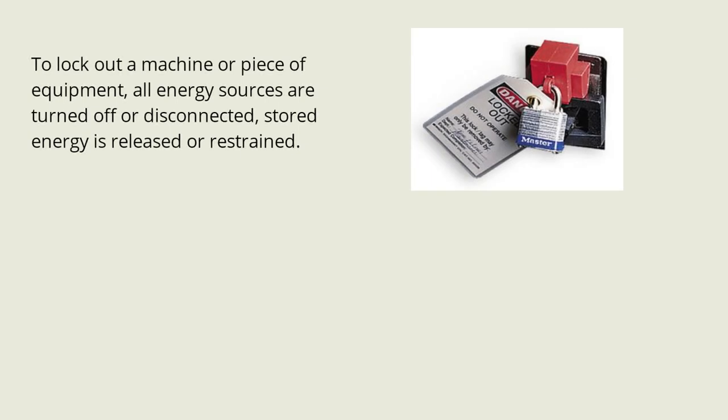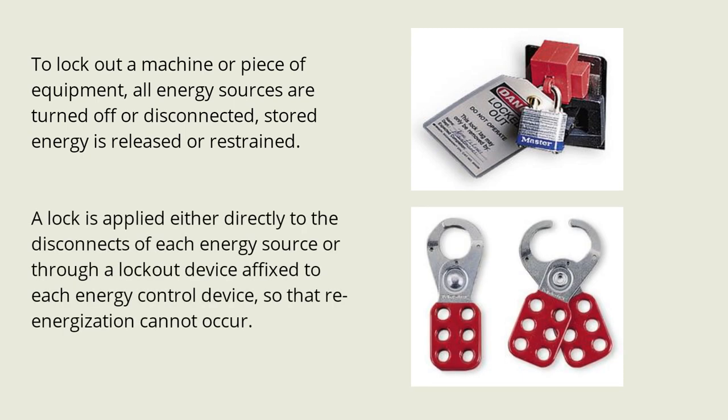To lock out a machine or piece of equipment, all energy sources are turned off or disconnected, stored energy is released or restrained, and a lock is applied either directly to the disconnects of each energy source or through a lockout device affixed to each energy control device, so that re-energization cannot occur.